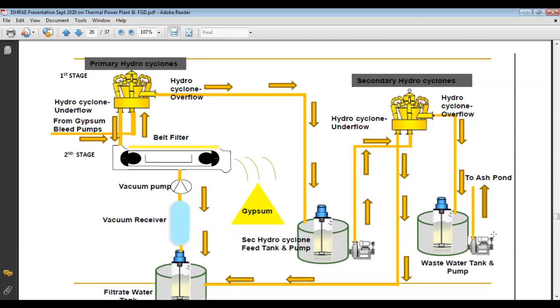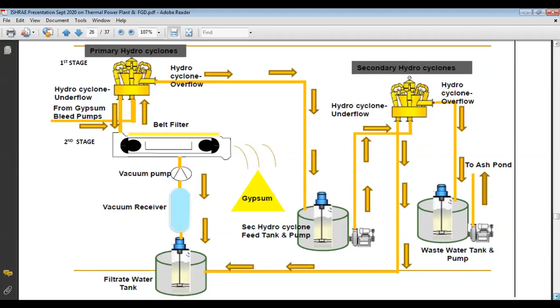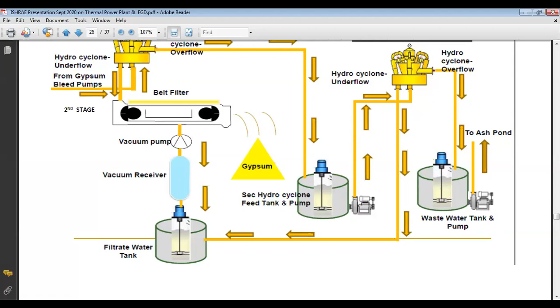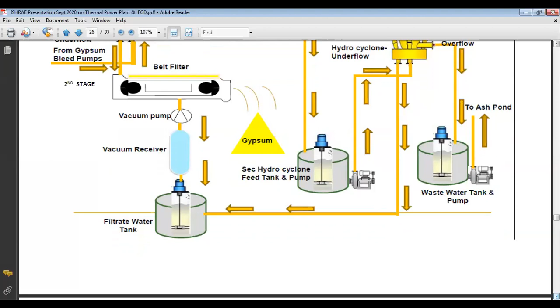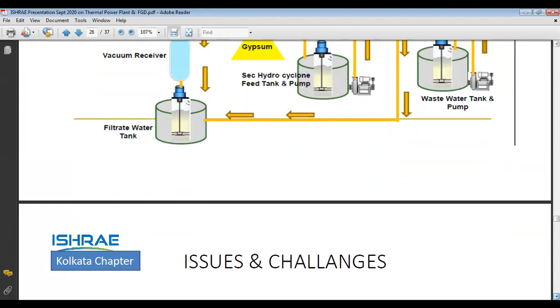You cannot waste water. So in those plants where ZLD is installed, this water can be pumped to the ZLD, where impurities, salts and heavy metals can be extracted, and the pure water is further taken into the main circuit of this FGD system. Finally, the water coming from this hydrocyclone and from the vacuum belt filter is collected into the filtrate water tank. From the filtrate water tank, it is recycled for slurry making and for absorber makeup also. So this water is reused in our circuit. Basically, for an FGD system, normally 0.25 to 0.30 cubic meters per hour per megawatt of water is needed.